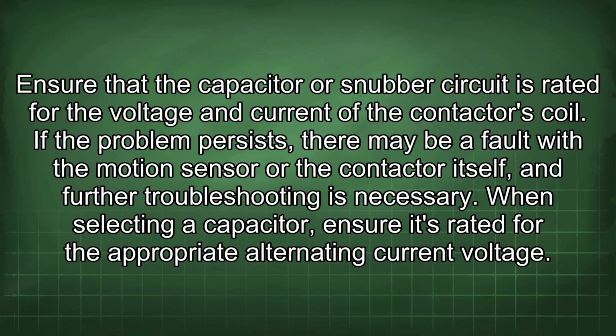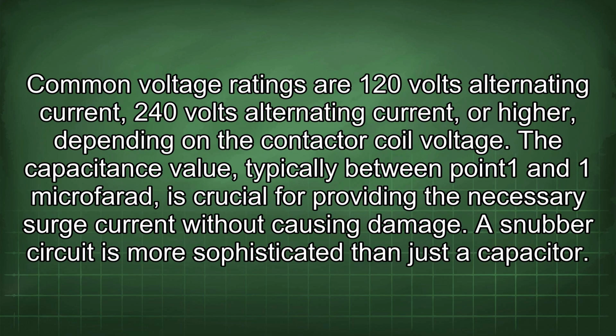If the problem persists, there may be a fault with the motion sensor or the contactor itself, and further troubleshooting is necessary. When selecting a capacitor, ensure it's rated for the appropriate alternating current voltage. Common voltage ratings are 120 volts alternating current, 240 volts alternating current, or higher, depending on the contactor coil voltage. The capacitance value, typically between 0.1 and 1 microfarad, is crucial for providing the necessary surge current without causing damage.